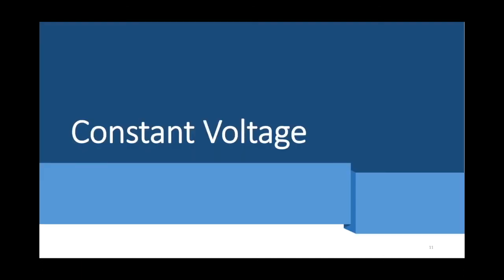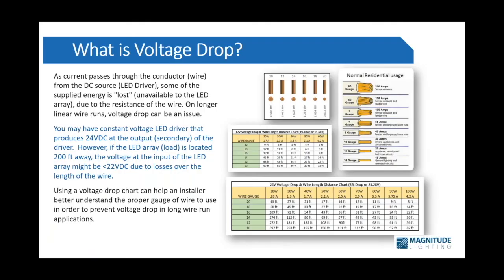So the first product line I want to get into is constant voltage. And before I speak about that, there's voltage drop. When you're working with constant voltage on longer runs, there will be some type of voltage drop, very minimum and not visually seen by the naked eye, but it does occur. As an example, as the current passes through the conductor, which is your actual wire gauge, and it goes through the DC source, which is your LED driver, some of that energy is lost by the resistance of the wire.